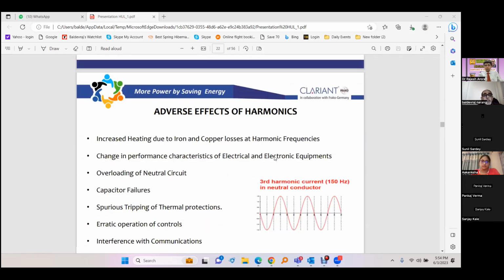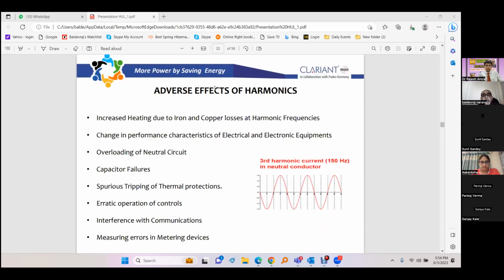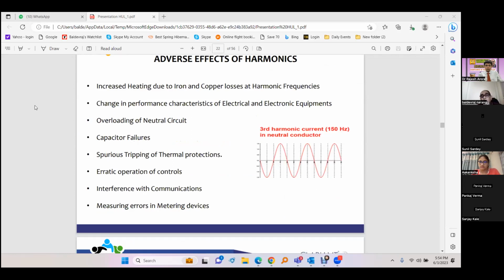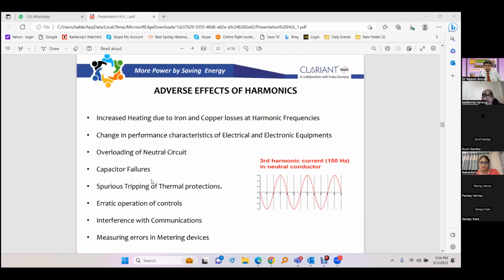So these are the adverse impacts of harmonics. There is increased heating because of the iron and copper losses, and the performance characteristics of all the equipment, electrical, electronic, change because they are not designed for harmonic currents along with the fundamental. Everything is designed for 50 Hertz. But when all these currents are also flowing, the characteristics change. Then the neutral, as I explained earlier, the neutral overloading is there. Capacitor failures are the first indication of the presence of harmonics because capacitors act as a sink for the harmonic currents.